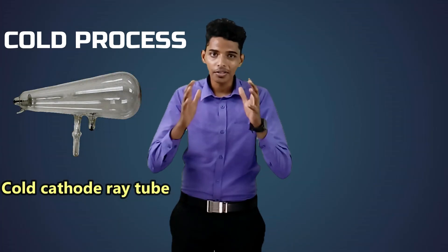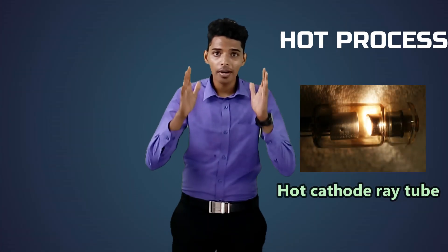To produce X-rays we need high-velocity electrons. These high-velocity electrons can be created by two processes. Number one is by ionizing the partially filled air inside the tube — this is called the cold process and is done in a cold cathode ray tube. Number two is by heating a heavy metal under high kV supply — this is called the hot process and is done in a hot cathode ray tube. In this lecture we are going to see the principles of X-ray production in the cold cathode ray tube.